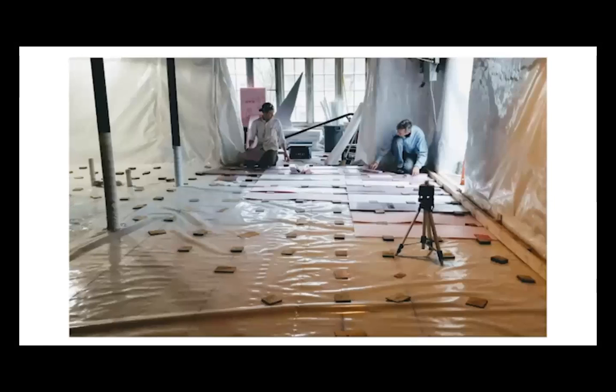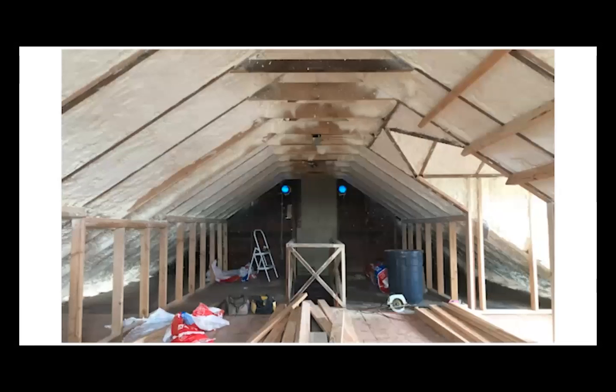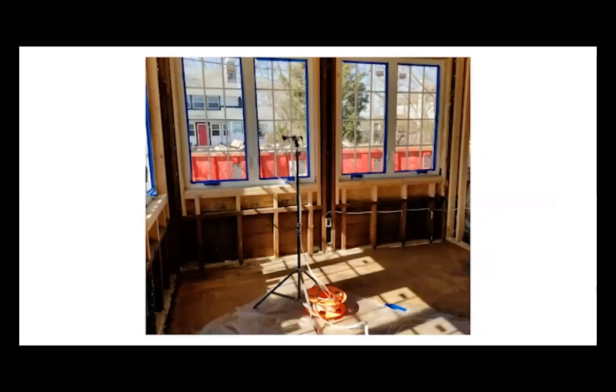We had fully lined the basement with taped poly. We had spray foamed the crawl space, but it just happens in some of those spaces. They normally won't do this approach in single family homes, because it has to be tight enough to begin with that you can actually pressurize. In order to spray this, they set up misting nozzles, and it basically sprays this water-based glue into the air. The fact that we knew we were already at 5 ACH50 was why they did it, because they knew they would be able to go on from there.